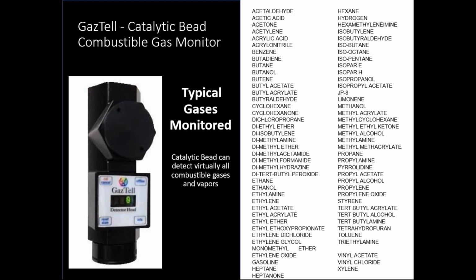Benzene is different than heptane, which is different than ethanol, which is different from Isopar H. Therefore, if you wanted to be accurate in detecting a specific gas, you would have to go into the sensor's submenu, the info menu, and set it up with a transfer factor specific to that gas.